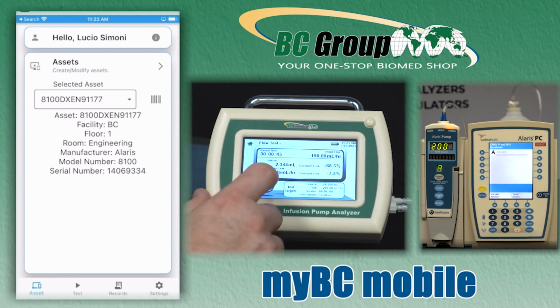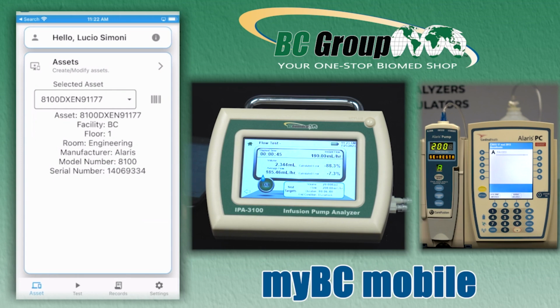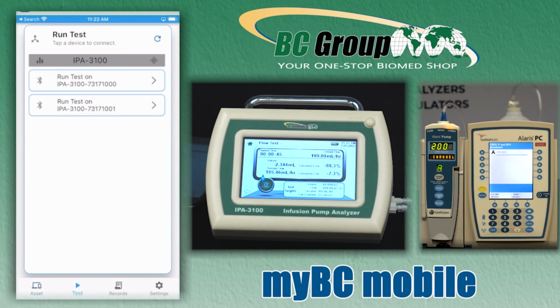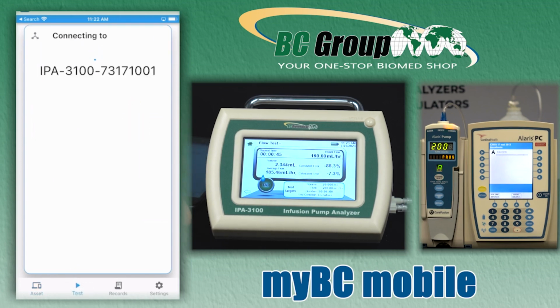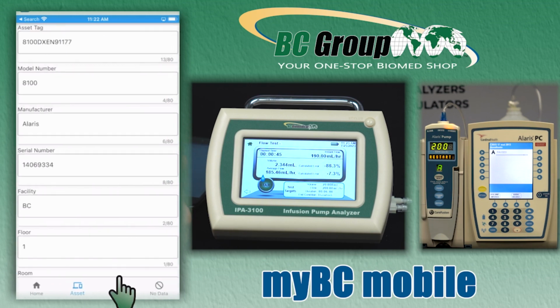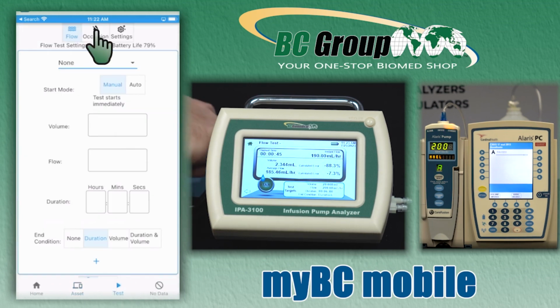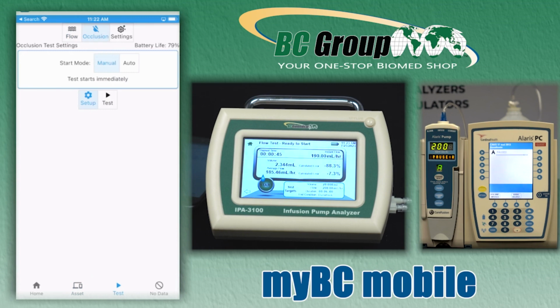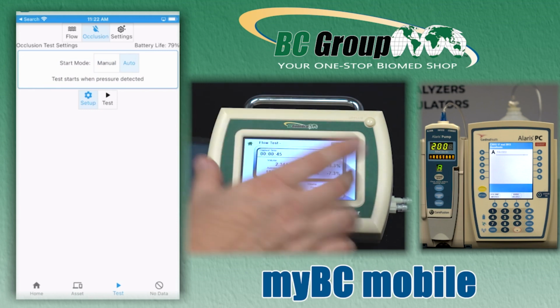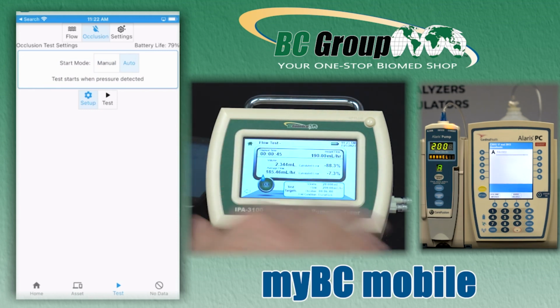So then we can go back to the myBC Mobile, and we'll say we're going to run another test on this instrument. And this time we're going to run an occlusion test. So we're going to show the settings here. Again, we have auto or manual start. I'm going to go to auto. And that's all I really need to configure on the BC Mobile. We'll show on the 3100. I'm just going to leave it on the screen.